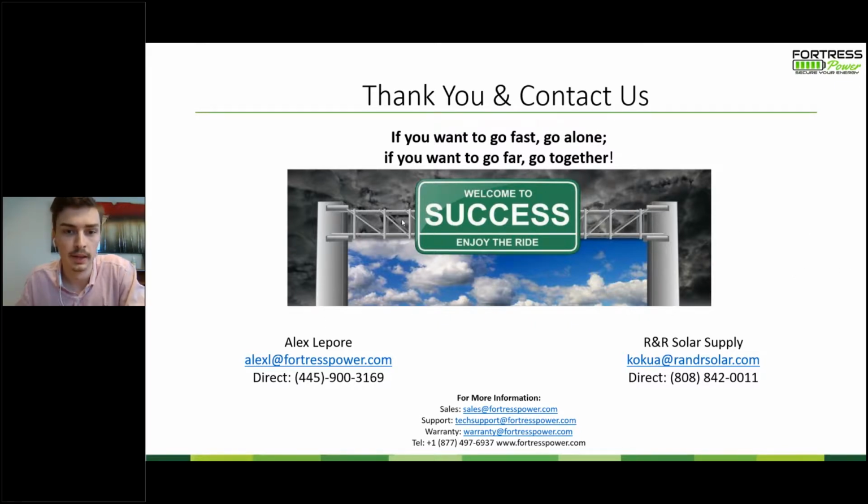There we go. Okay. Brian had another question: can you talk about points when compared to Tesla and Generac? Absolutely. The main comparison I make with the Tesla system is the chemistry. Having cobalt is good, I think, in certain applications, like their electric vehicles. You need a very dense battery to move the car from point A to point B. But in or near somebody's home, that's where using LiFePO4 has more advantages because it has longer life cycles, 6,000 cycles compared to maybe 3,500 cycles. And there is a much, much lower chance of thermal runaway just because we do not have that added element of cobalt.